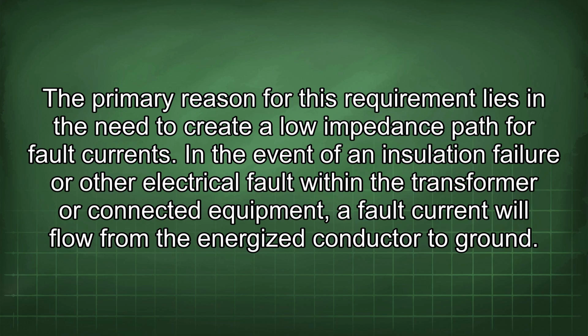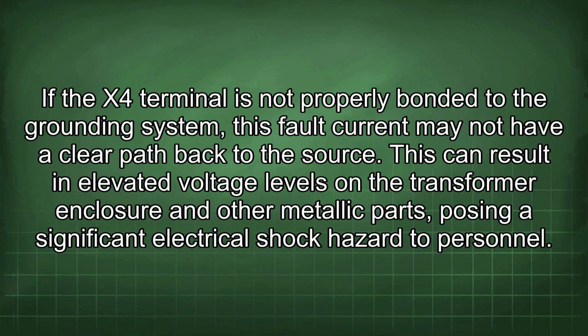In the event of an insulation failure or other electrical fault within the transformer or connected equipment, a fault current will flow from the energized conductor to ground. If the X4 terminal is not properly bonded to the grounding system, this fault current may not have a clear path back to the source. This can result in elevated voltage levels on the transformer enclosure and other metallic parts, posing a significant electrical shock hazard to personnel.